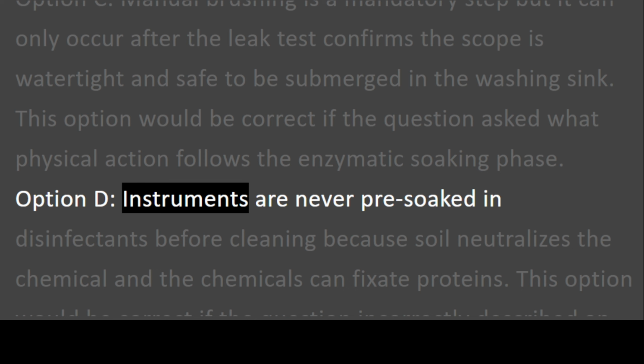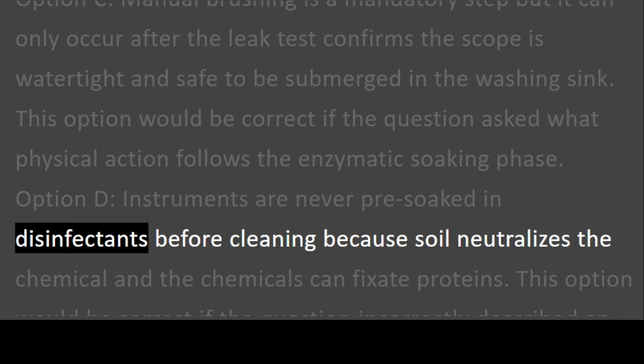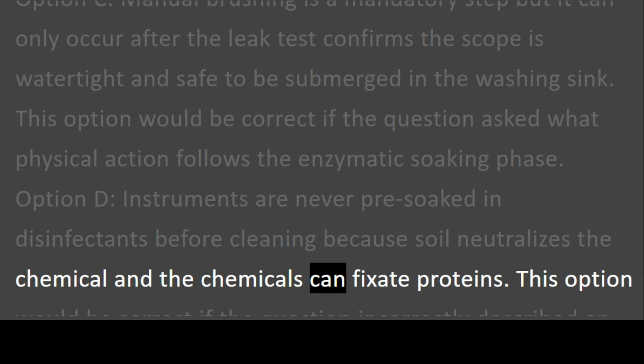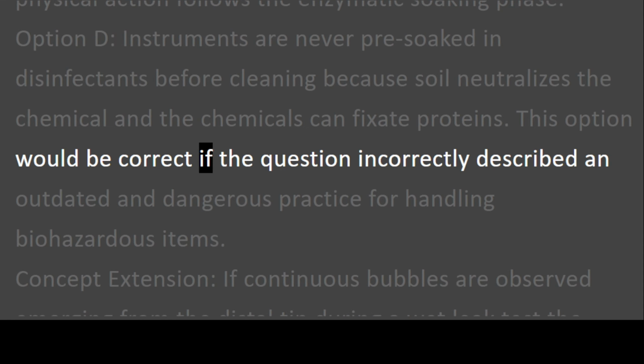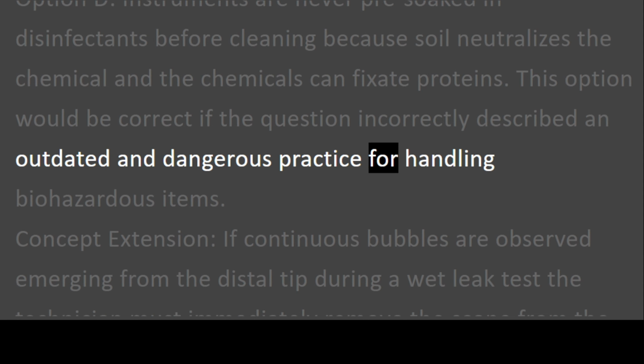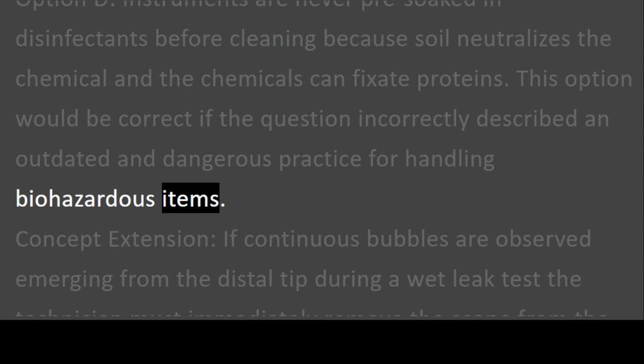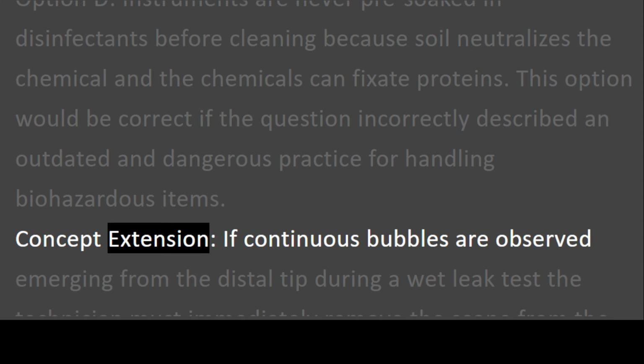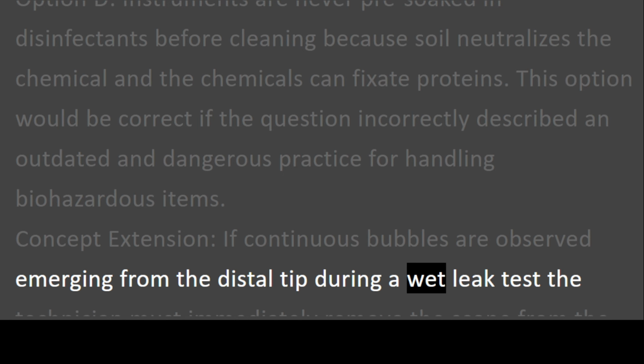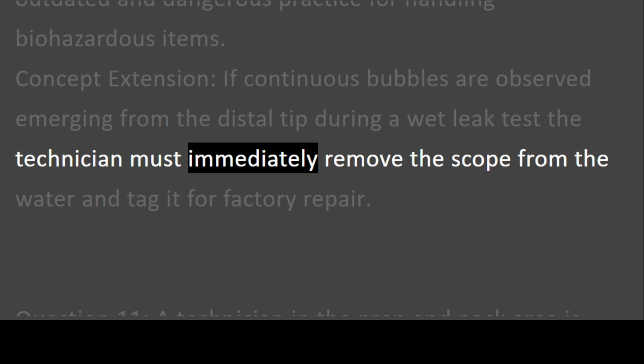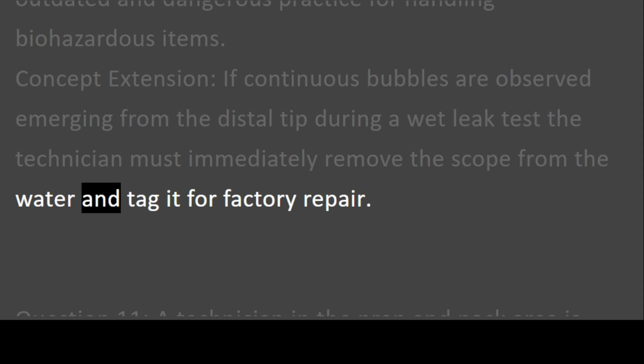Option D. Instruments are never pre-soaked in disinfectants before cleaning because soil neutralizes the chemical and the chemicals can fixate proteins. This option would be correct if the question incorrectly described an outdated and dangerous practice for handling biohazardous items. Concept extension. If continuous bubbles are observed emerging from the distal tip during a wet leak test, the technician must immediately remove the scope from the water and tag it for factory repair.